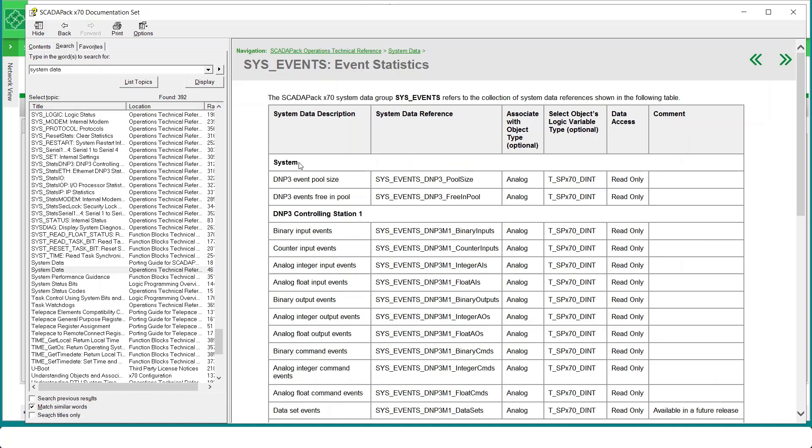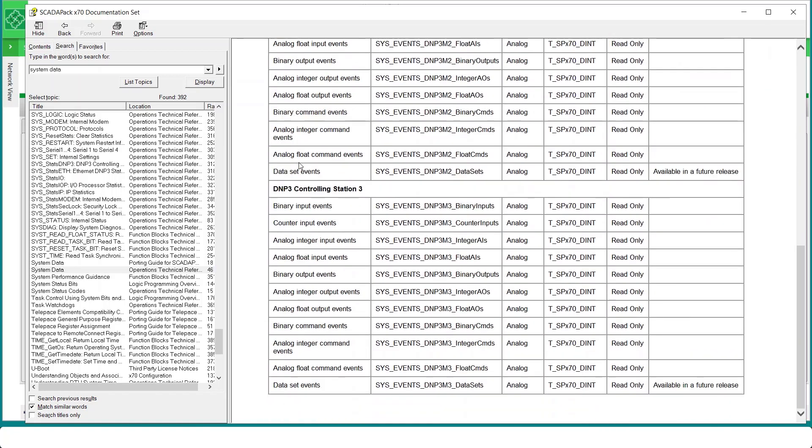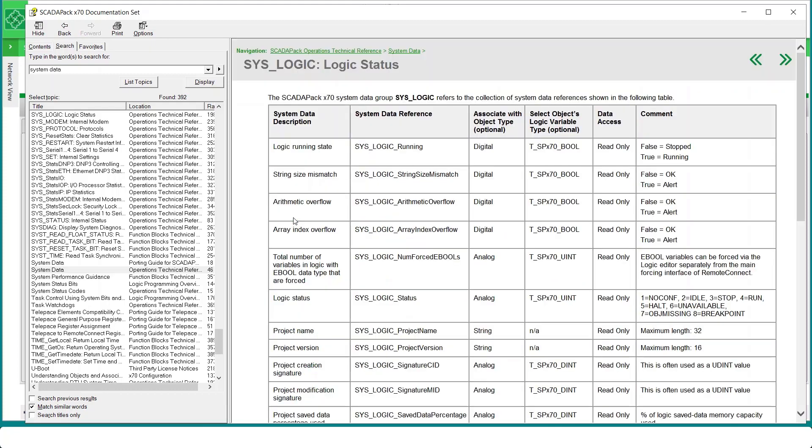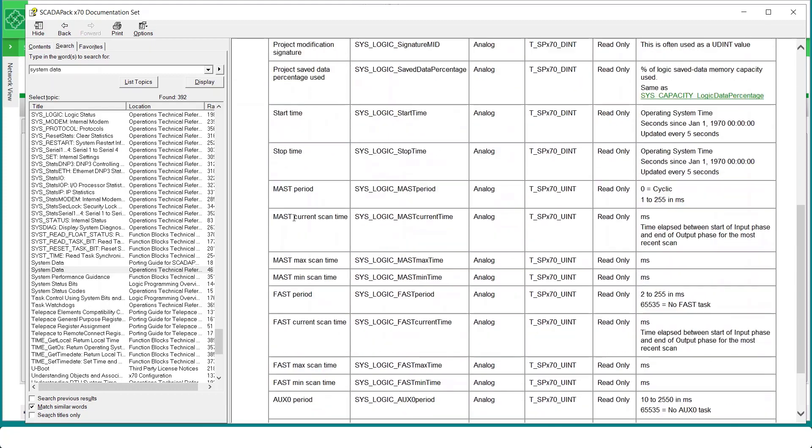And perhaps we wanted SysLogic. Click on that. And here is a very helpful item. SysLogic MAST Current Time will give us the last scan time of the main or MAST program in the Remote Connect logic. There are other parameters such as the MAST Max Time and Min Time.